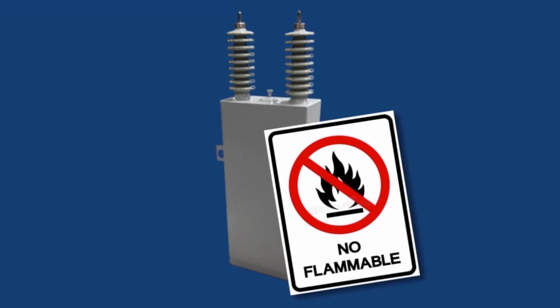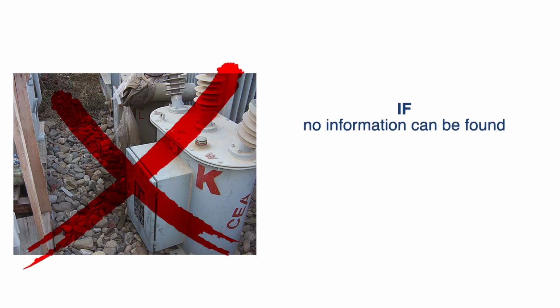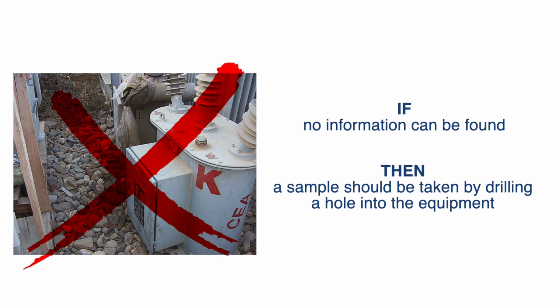Some capacitors have a label or plate indicating non-flammable liquid or non-flammable synthetic oil. This would indicate the presence of PCB and needs to be tested. If no information can be found on the type of oil, brand, or manufacturer, then a sample should be taken by drilling a hole into the equipment. In this situation, the capacitor can no longer be used and must be disposed of properly.